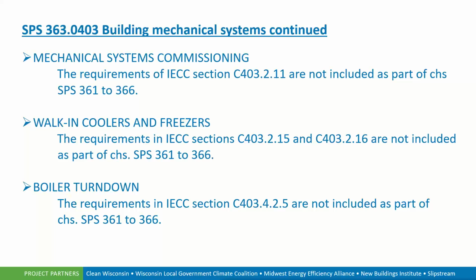Now, there are sections that were deleted from the IECC. This is a fairly big one: mechanical systems commissioning. The requirements of IECC 2015 section C403.2.11 are not included in SPS 361 through 366. Walk-in coolers as well. Sections 403.2.15 and 403.2.16 are not included. And boiler turndown requirements. These are some pretty significant items that were not included in the code, so just be aware that these are sections that are not part of the code.